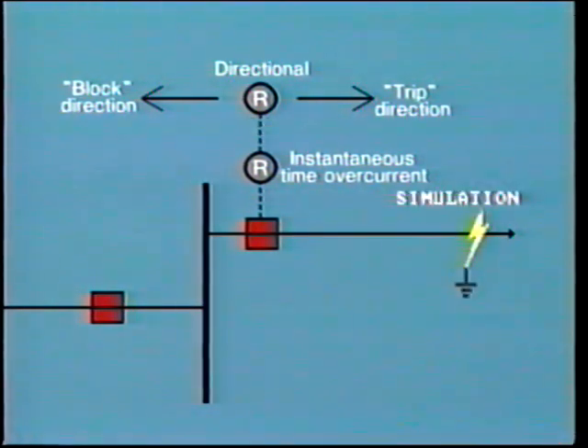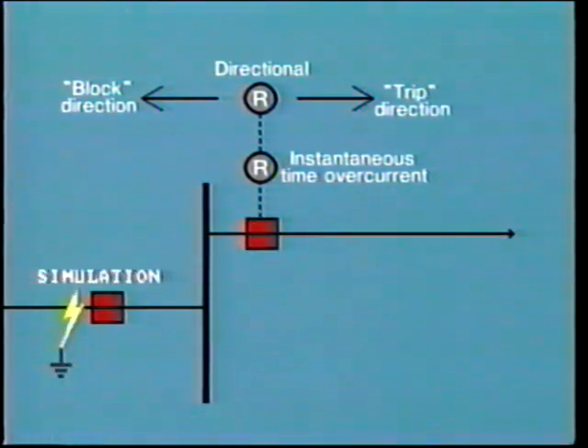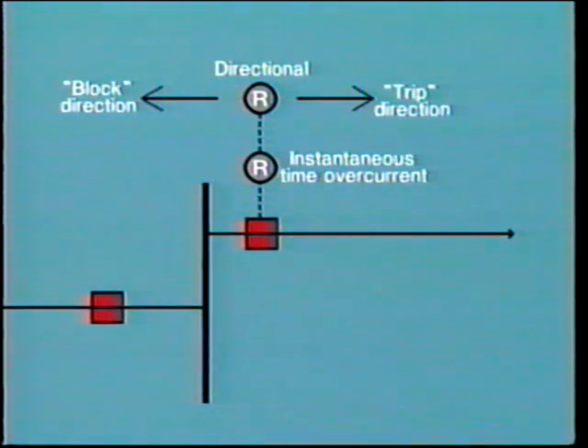After this, simulation tests were performed and the protection operated correctly to trip for faults in the operate direction. This was expected. However, what was not expected was that for faults in the reverse direction, the directional elements still allowed false tripping to occur when it should have acted to prevent operation. Further detailed testing showed the reason for this.